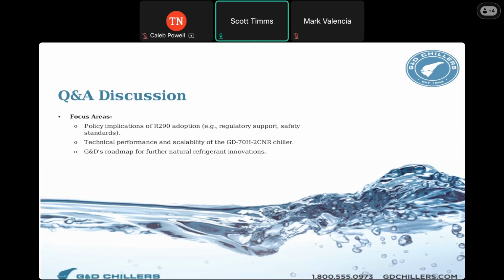I think that things have gotten a lot better in the brewery and distillery space as far as installation goes, but even 5 years ago, the level of education within these spaces, especially the craft spaces, was a lot lower. The biggest thing you can do is insulate your glycol piping. I've been in a lot of breweries that just have glycol pipes that are sweating because they're not well insulated. Anytime you see condensation on a pipe, that's heat coming into the system - quite a bit of heat, honestly - that the chiller has to keep up with, and that's going to reduce your efficiency by quite a bit.